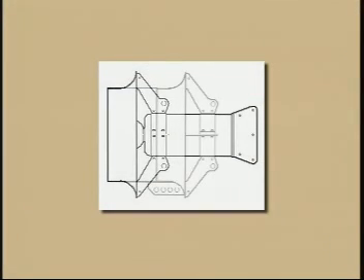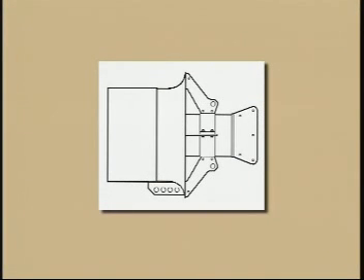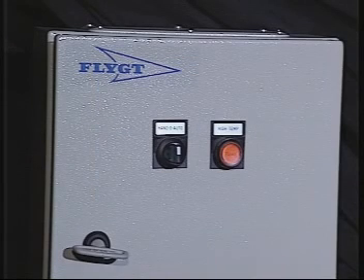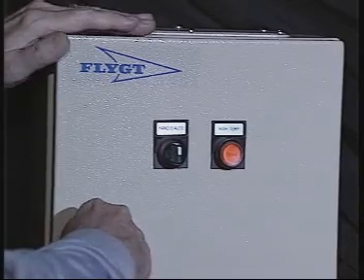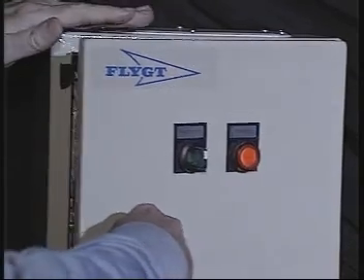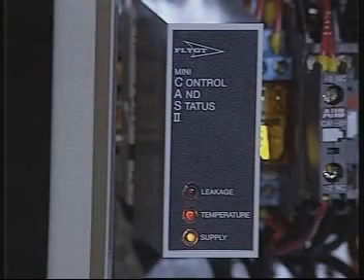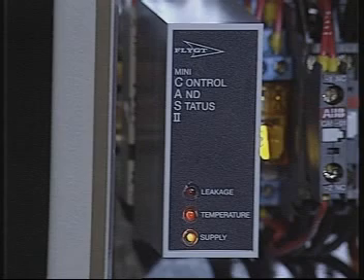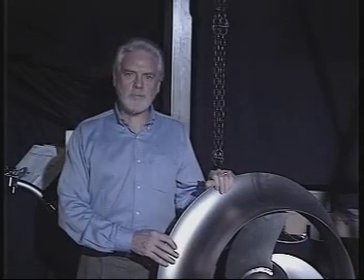Special jet rings, extended jet rings, should be used in thick mud in order to pull flow around the mixer and keep it cool. If the indicators in your control panel generate an alarm, do not ignore the alarm or override it. Attend to the problem to avoid unnecessary breakdowns. Before starting work, make sure the mixer is isolated from the power supply and can't be energized.